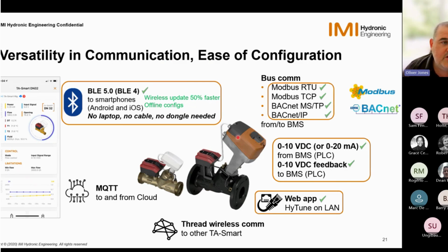So versatility in communication. So this is just to show off really and reiterate the types of communication that we have within the unit itself. On the left hand side is a screenshot from our HyTune app itself. So this is the screen you will see when you're connected and interfacing with the valves themselves. This is all done over Bluetooth 5.0, so on Android or iOS. So no cables, no laptops or dongles needed. Bus communication, so we can do Modbus and BACnet. We can do Modbus RTU and BACnet MS/TP, and we can also do Modbus TCP and BACnet IP.